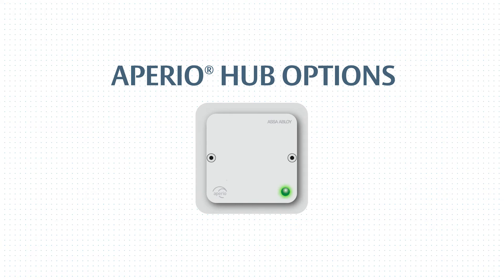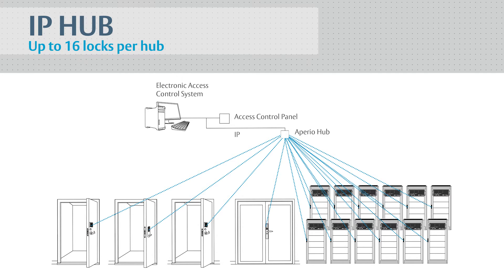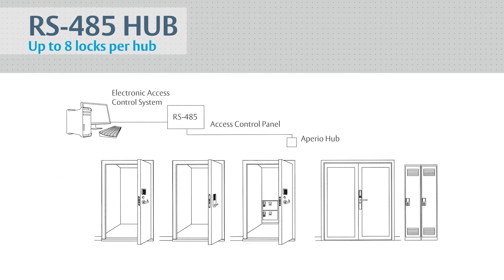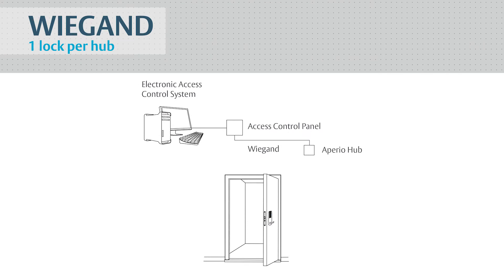Aperio hubs come in a variety of configurations to ensure easy integration with your existing access control systems. The IP Aperio hub uses standard Ethernet cabling to connect to IP access control systems and supports up to 16 devices per hub. The RS-485 hub connects to an RS-485 access control panel and supports up to 8 locks per hub. The mercury-powered hub connects to any mercury-powered controller and supports up to 8 locks per hub. The Wiegand hub connects to industry standard Wiegand access control systems and can support a single lock.